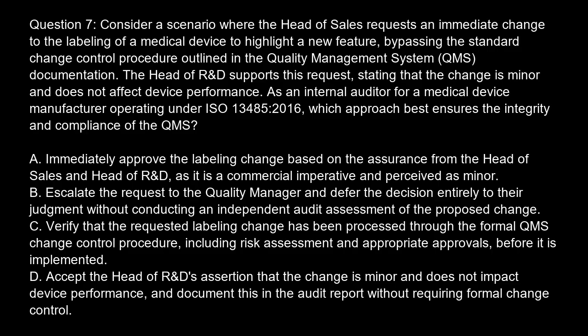Option A. Immediately approve the labeling change based on the assurance from the head of sales and head of R&D, as it is a commercial imperative and perceived as minor. Option B. Escalate the request to the quality manager and defer the decision entirely to their judgment without conducting an independent audit assessment of the proposed change. Option C. Verify that the requested labeling change has been processed through the formal QMS change control procedure, including risk assessment and appropriate approvals, before it is implemented. Option D. Accept the head of R&D's assertion that the change is minor and does not impact device performance, and document this in the audit report without requiring formal change control.